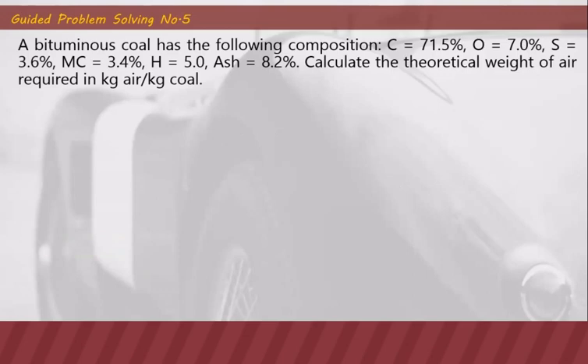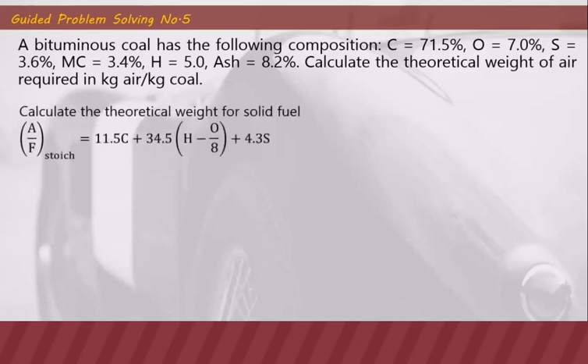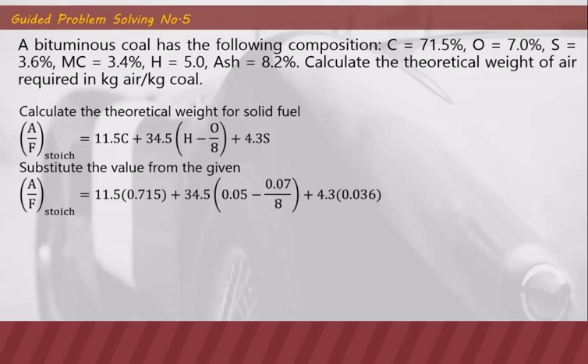Guided problem solving number five: a bituminous coal has the following composition — carbon 71.5%, oxygen 7%, sulfur 3.6%, moisture content 3.4%, hydrogen 5%, ash 8.2%. Calculate the theoretical weight of air required in kg-air per kg-coal. Using the stoichiometric air-fuel ratio formula for solid fuel — 11.5C + 34.5(H − O/8) + 4.3S — and substituting decimal values, the stoichiometric air-fuel ratio is 9.8 kilograms of air per kilogram of fuel.